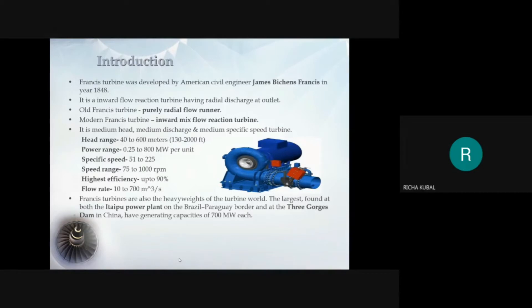At the entrance to the runner, only part of available energy of water is converted into kinetic energy and the substantial part is in the form of pressure energy. The pressure energy at inlet is much higher than pressure at outlet. The pressure difference between inlet and outlet of runner is called reaction pressure, and hence the turbines are called reaction turbines.